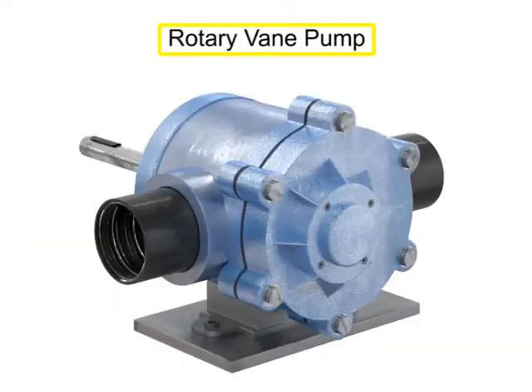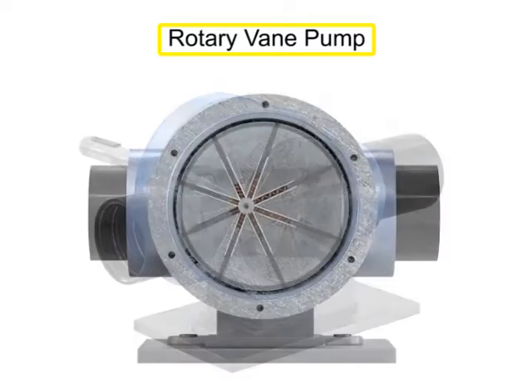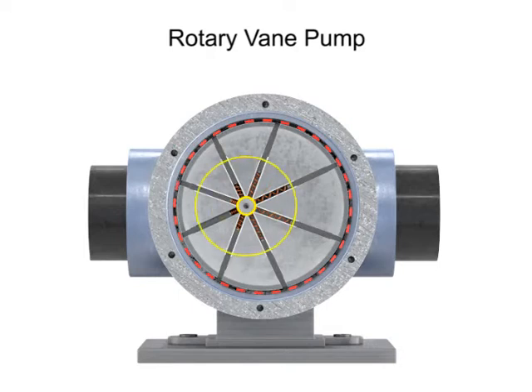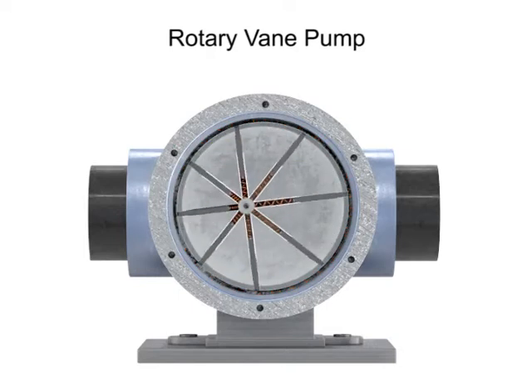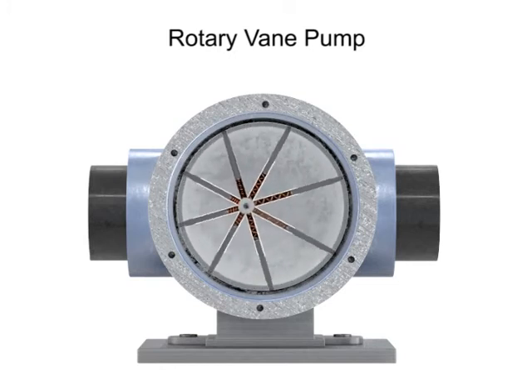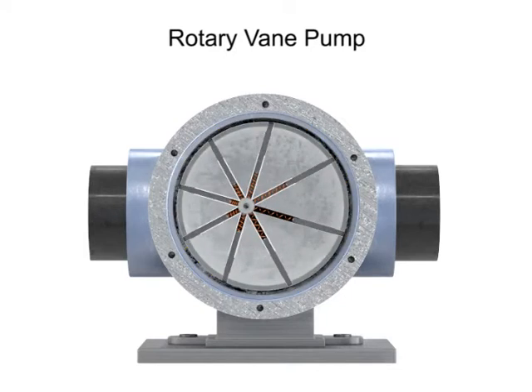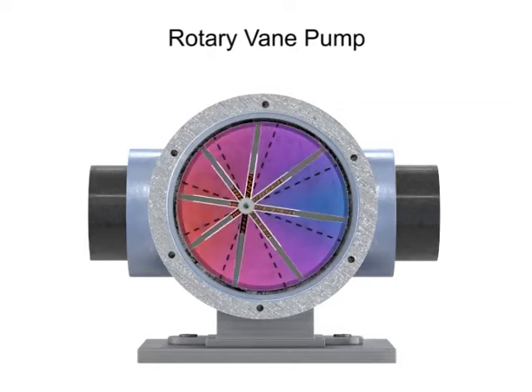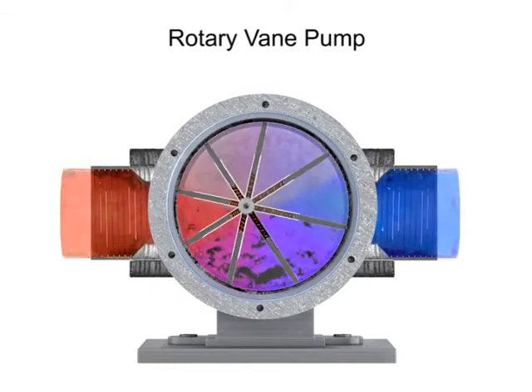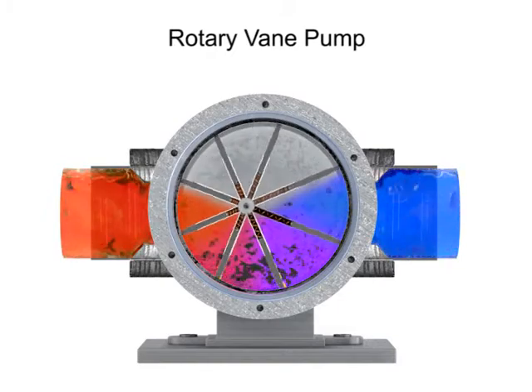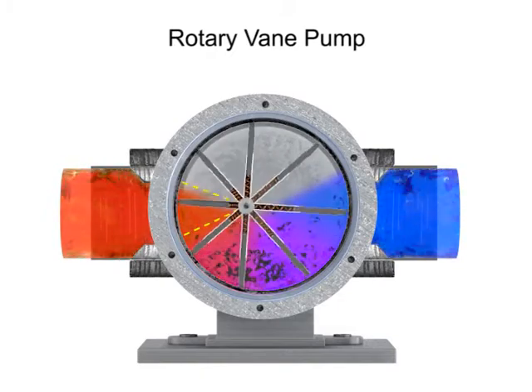A rotary vane pump is a positive displacement pump that consists of vanes mounted to a rotor. The vanes are on an off-center drive shaft. As the shaft rotates, the variable length vanes slide in and out to maintain contact with the pump housing. The tension in the vanes is maintained by either springs or hydraulic pressure. As the vanes rotate, they create chambers of varying sizes within the pump. Fluid enters at the largest chamber, and as the vanes rotate and retract, the chambers get smaller, forcing fluid to exit through the discharge port.